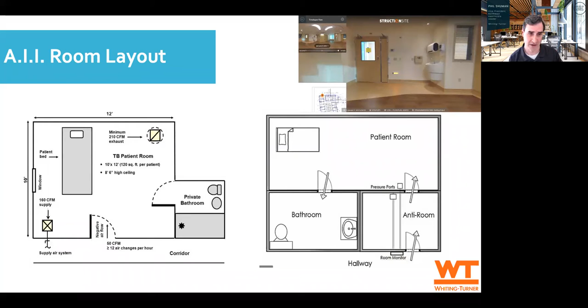You really want that over the patient bed, because for any droplets that are coming out of a contaminated person's mouth, you want to minimize the chance that any currents in the air could have those droplets go by the medical practitioners. Additionally, when you do not have an anteroom, you want to be cognizant that every time you open and shut that door, you're going to create some eddies, and some of the air inside the room will go out towards the corridor. So it's important to keep in mind the airflow within the room itself. Slide, please.